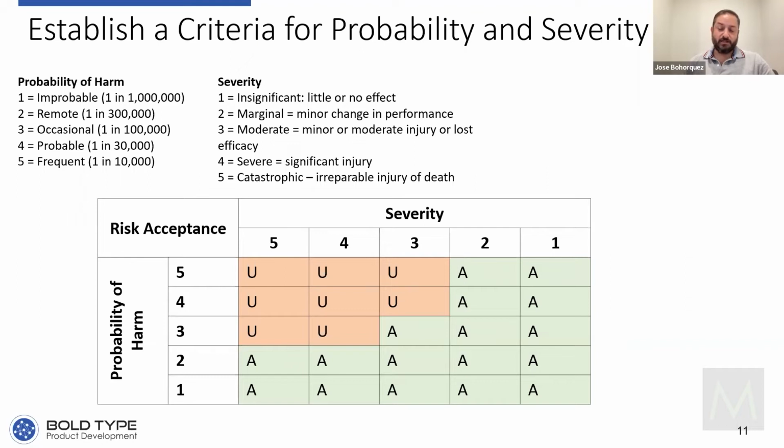And then post-launch, this is an important point, risk management doesn't end after you've launched the product. You've got a certain responsibility as you learn new things from the field to come back and reassess things, because there may be a failure mode that you expect to be low probability, and so it's an acceptable risk. And then you start getting field data telling you that this happens more than you were expecting.